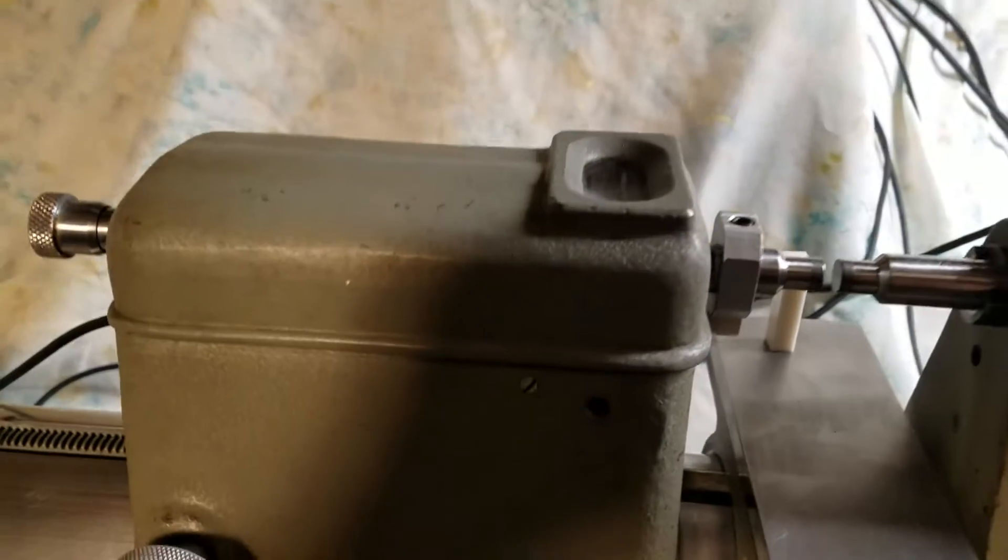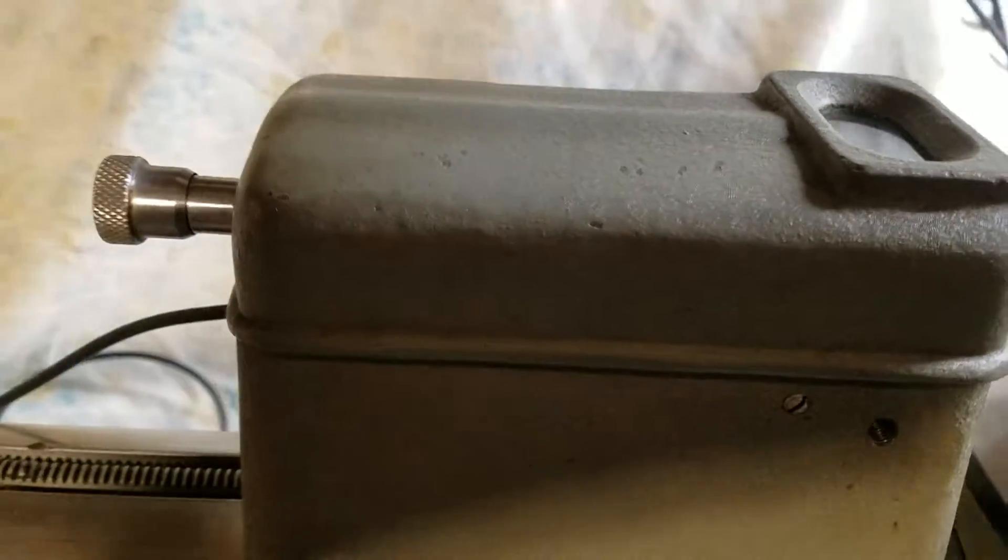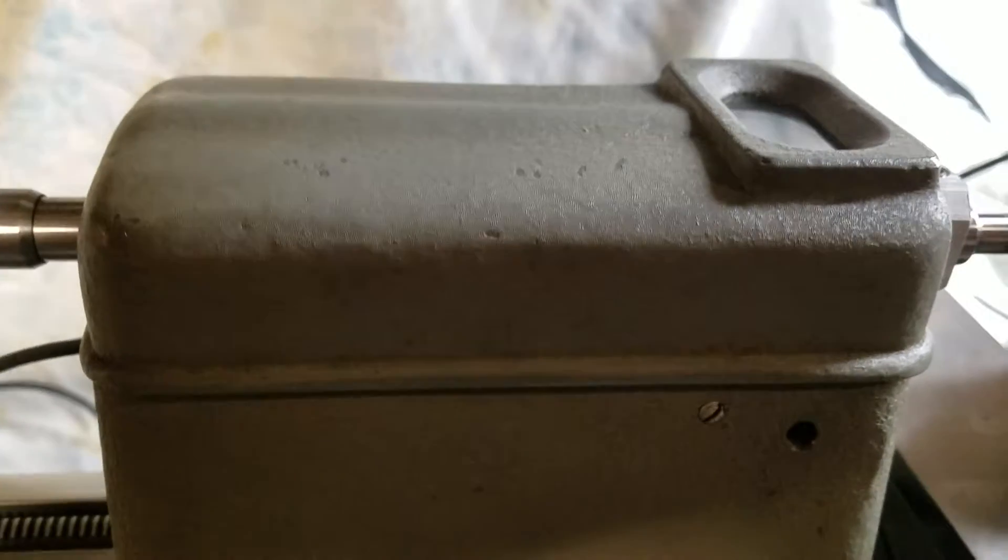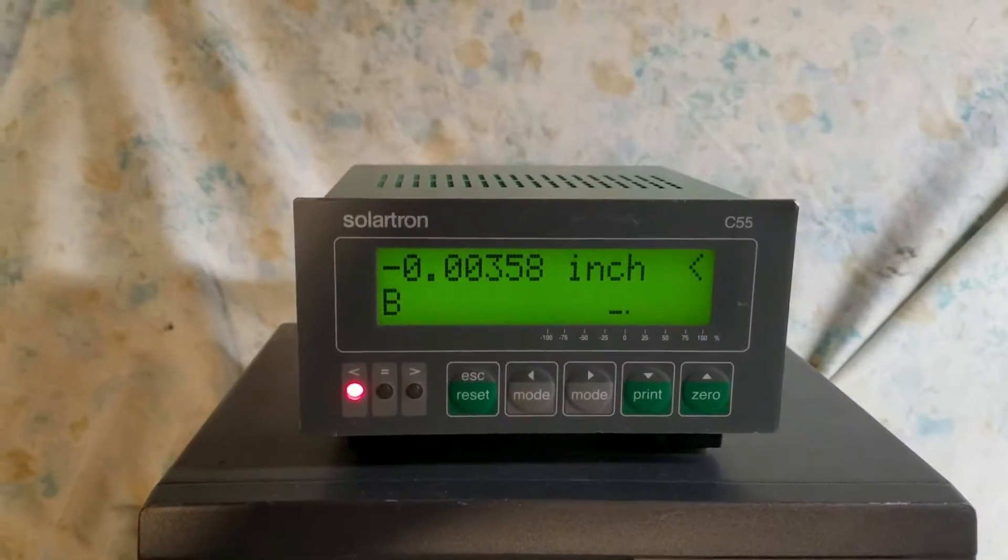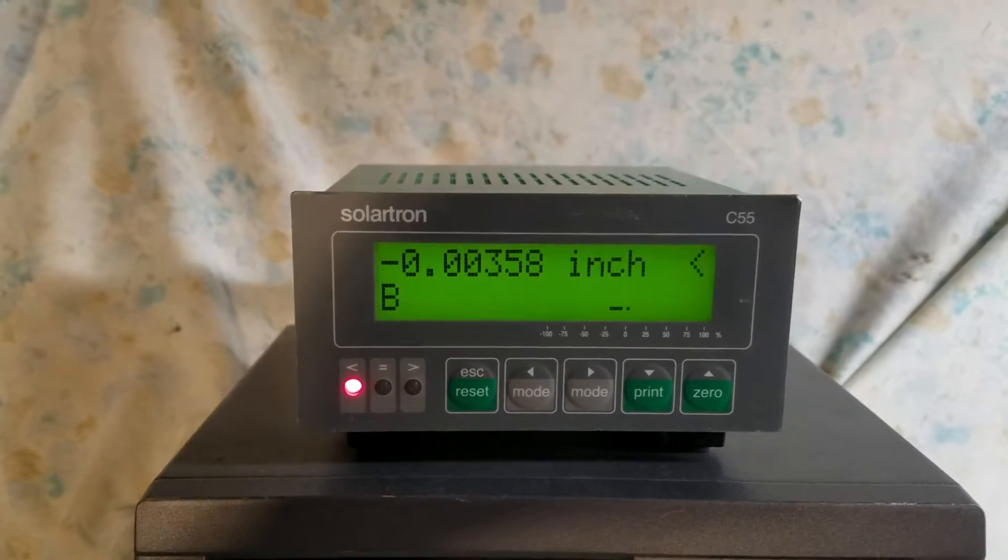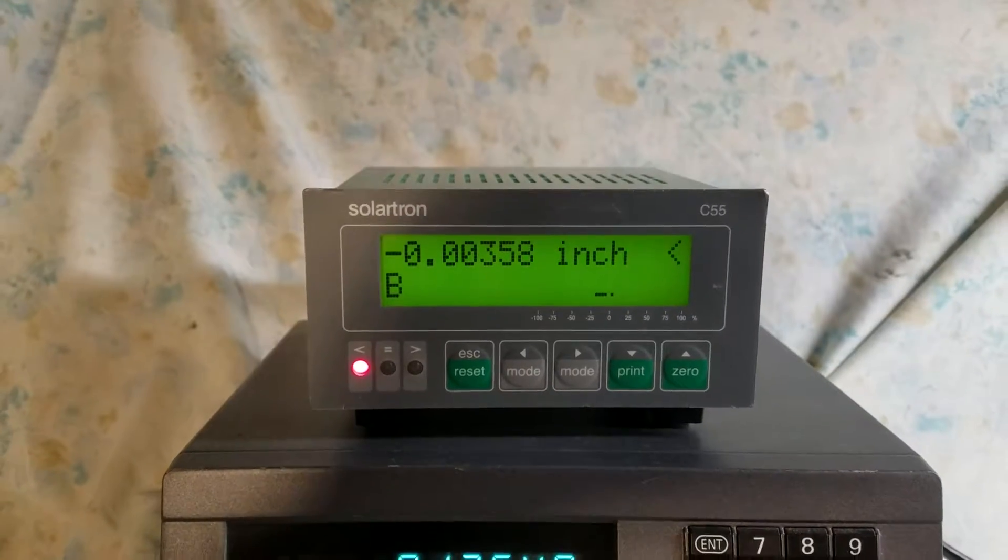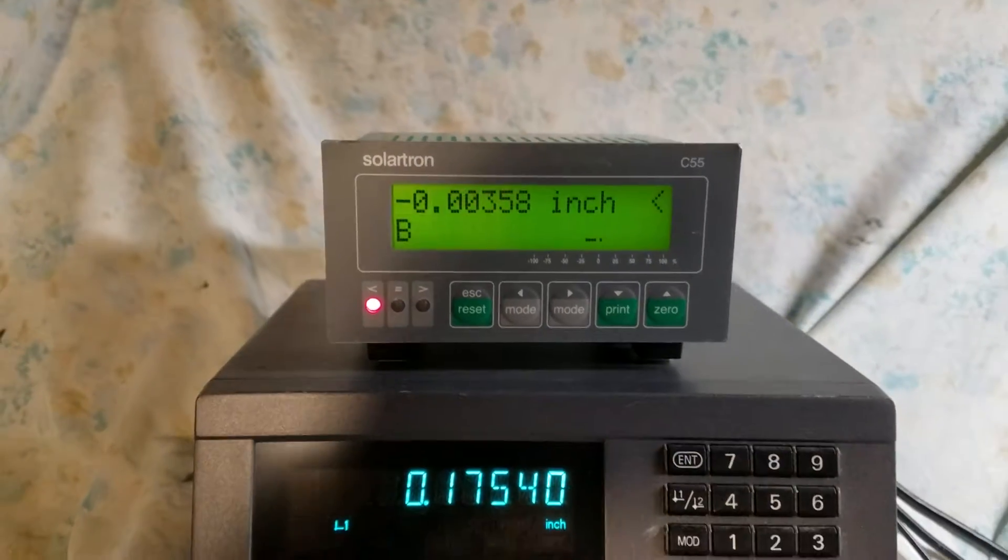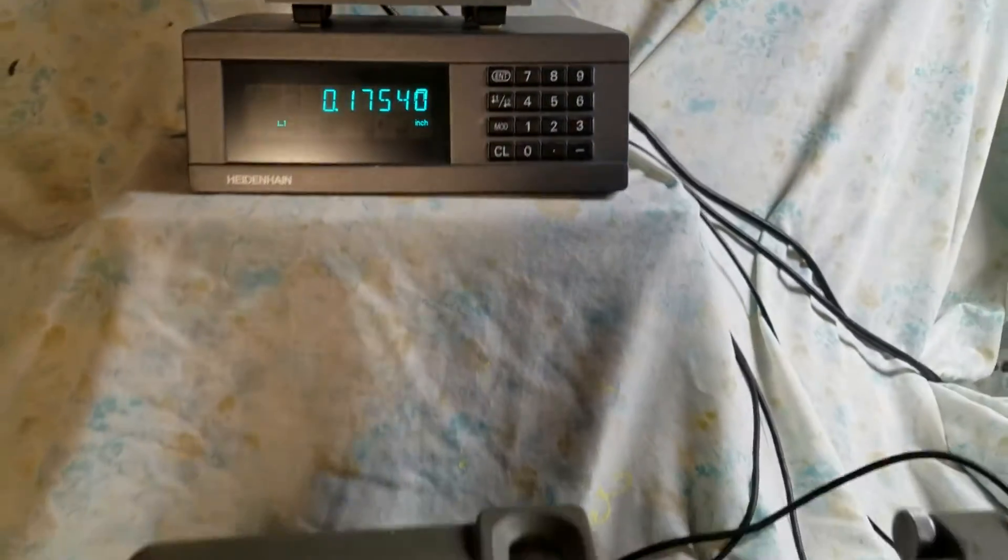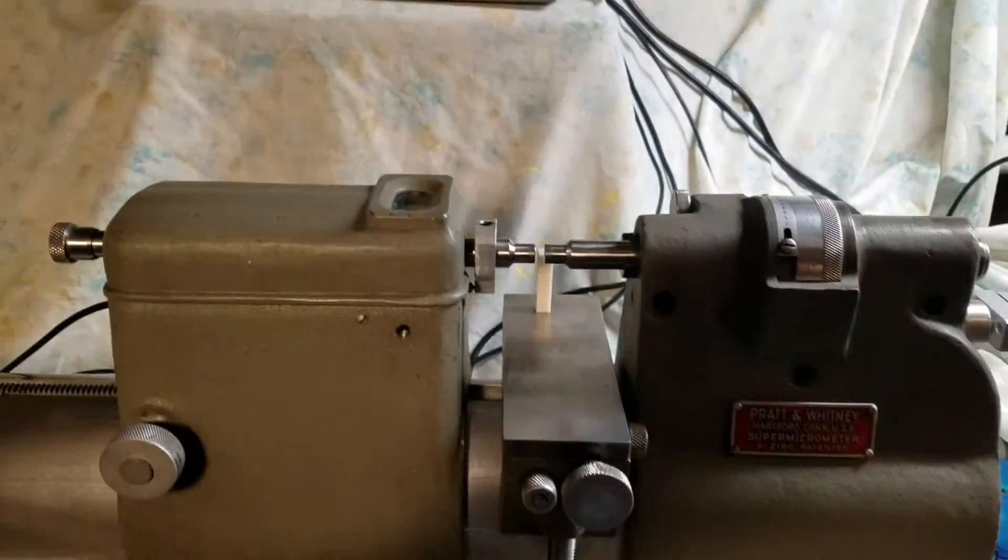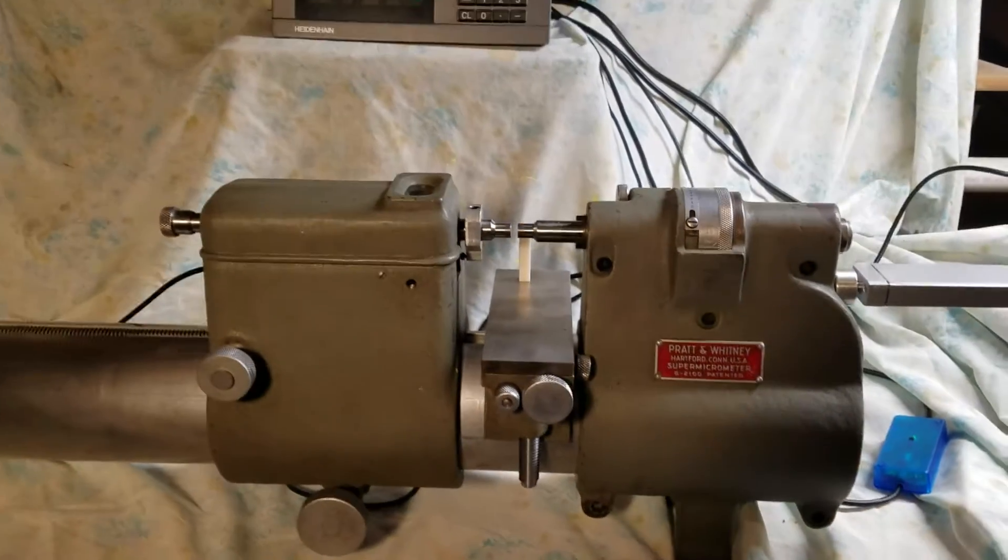The tail stock has been retrofitted with a high accuracy LVDT probe, also utilizing a digital display to set the zero point. This ensures the tail stock position returns exactly to the point where it was mastered and, in turn, ensures the force stays the same for each measurement.